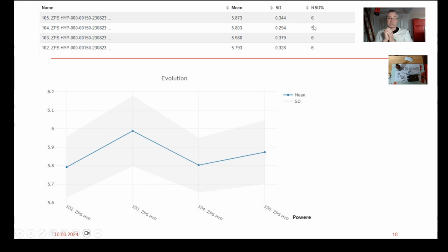So that's the repeatability. People use that word repeatability. I'm not sure, I might want to use the word reproducibility, but we check that before we actually ship it. So this is single digits. Relative standard deviation is 6.566%. It's really important. So we don't often do calibration when we're shipping our true products, not the R&D products, not the stuff that we put on the website, but the screen printed electrodes, which are definitely high volume products from ZP, and we definitely do a lot of in-house testing.